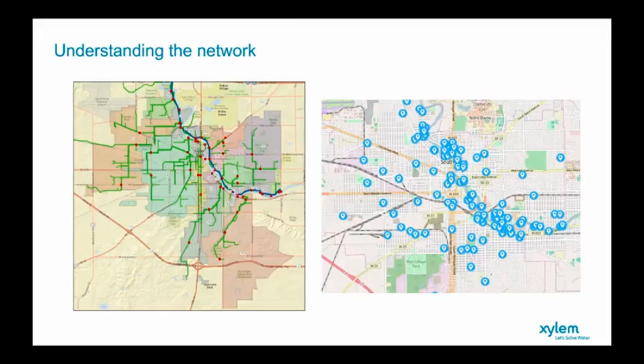A lot of the things that are based on assumptions of the hydrology, such as the percentage impermeable area and what type of antecedent conditions are being used, can be stripped out of models and replaced by artificial neural networks if appropriate. So hydraulic models don't have to be used in these approaches, but they can be very useful to provide information about locations where there aren't any sensors. You can't put a sensor everywhere in the network, and if you want to know what might be happening in a location where there isn't a sensor, a hydraulic model can be useful in providing that information.